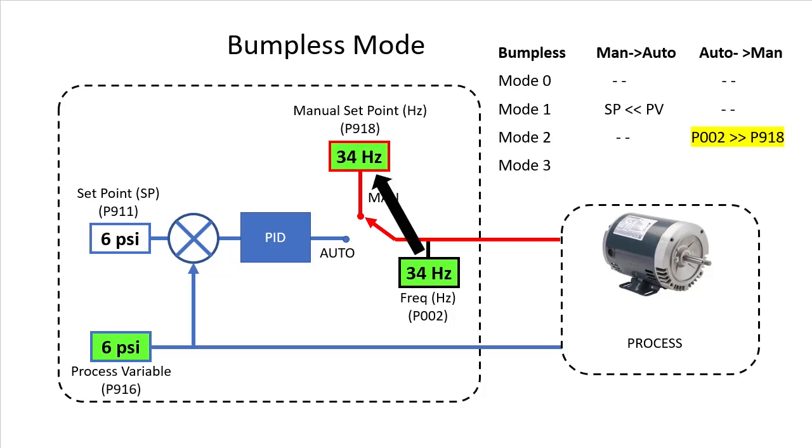Bumpless mode 2 sets the manual set point to whatever the current drive frequency is, so when you make the switch to manual mode the motor just keeps spinning at whatever speed it was already at, again preventing a sudden change.